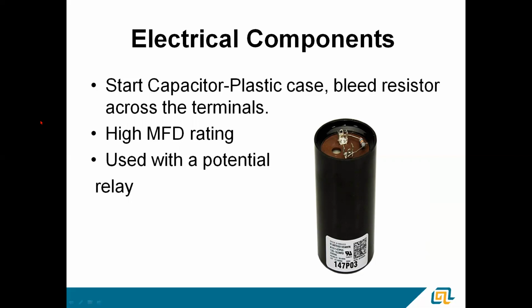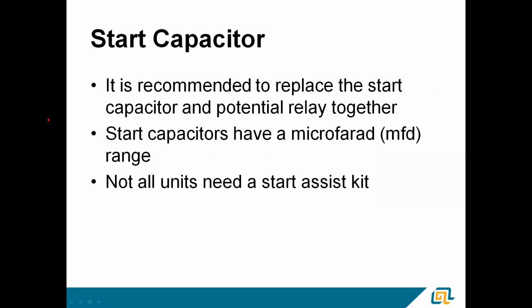The potential relay removes the capacitor from the starting circuit once that compressor starts. One thing about starting components, you can't just substitute universal stuff for it. The start capacitor and the start relay are extremely model specific, so you have to make sure what you're putting in there is the same thing that was in there. It's recommended to replace the start capacitor and a potential relay together. Whichever single component you might find has failed, you really want to replace them both. The potential relays can easily be damaged if they're held in the start winding too long. And if that's the case, the capacitor can be damaged as well.